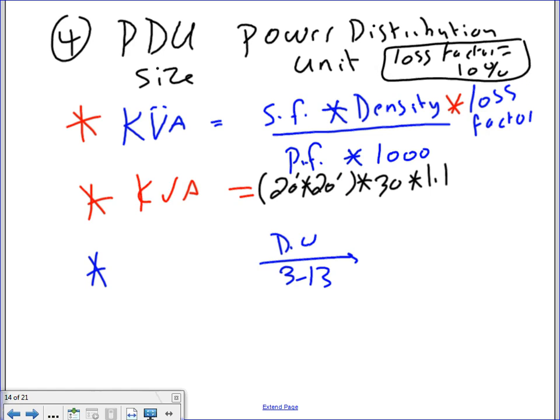So here's where the 1.1 comes in, divide everything here by the power factor. What's the power factor? Same power factor, 0.9. Multiply this baby by 1,000 to convert it. And Kieran, what did we come up with again? The same number should be 14.67 kVA.